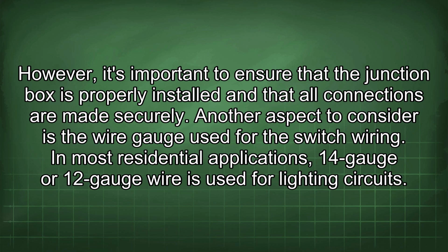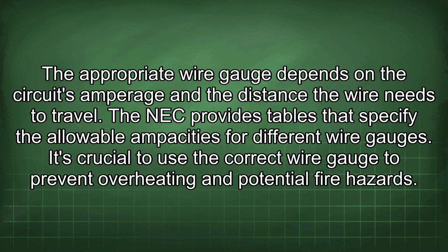Another aspect to consider is the wire gauge used for the switch wiring. In most residential applications, 14-gauge or 12-gauge wire is used for lighting circuits. The appropriate wire gauge depends on the circuit's amperage and the distance the wire needs to travel. The NEC provides tables that specify the allowable ampacities for different wire gauges. It's crucial to use the correct wire gauge to prevent overheating and potential fire hazards.